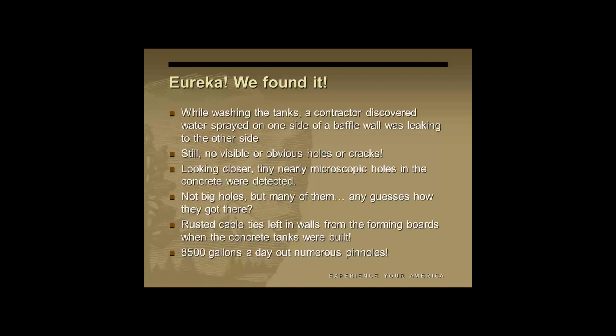As a person was washing down one side of that wall, the other side was actually getting wet. We couldn't figure that out, since the water had to travel through 10 inches of concrete from just a garden hose. We started looking closely and found the water was coming through tiny holes all through the wall, from rusted-out form ties. When they poured these concrete tanks, they formed the walls and poured them in place, holding the forms together with cable ties. Over the years those cable ties rotted out, probably aided by the fact that we chlorinate the water, and had actually rotted through, creating those holes.